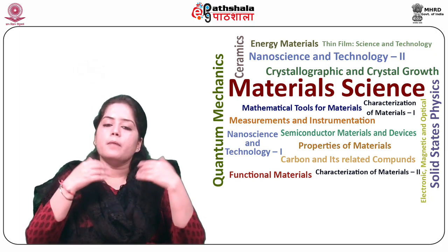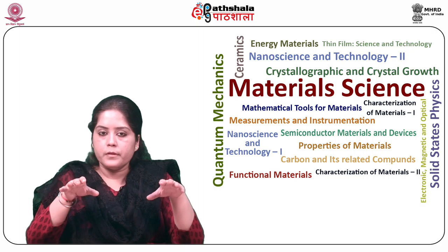Vacuum system: the microscope column and the specimen chamber are kept under high vacuum, that is 10⁻³ to 10⁻⁴ Pascal. A diffusion pump is used to evacuate these components. For an oil-free environment, a turbo molecular pump is used. For FESEM, a sputter ion pump is used as FESEM operates at ultra high vacuum.